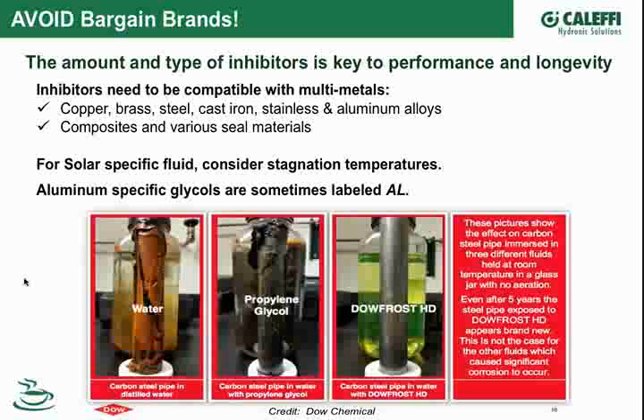So at the end of the day, get a product that's designed for the materials you're using, and you can see the pictures here of what happens when you don't. If you just have plain water, or just put plain glycol in that plain water, you're guaranteed to have a corrosion problem. Those examples are for carbon steel, but I could show pictures of other metals too.